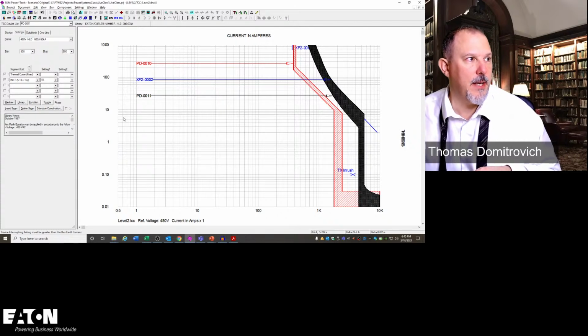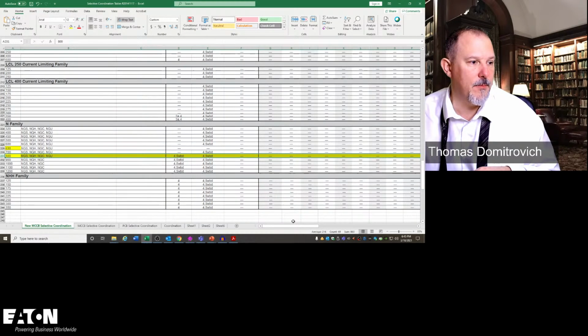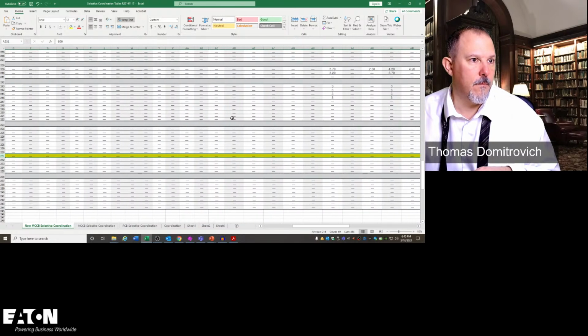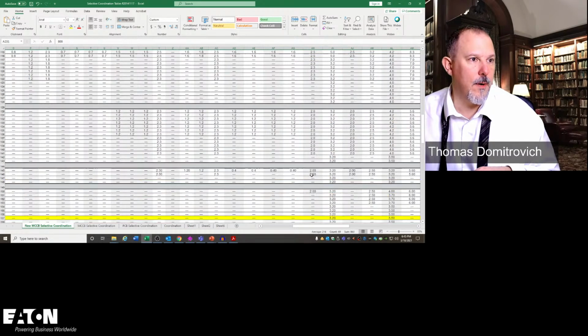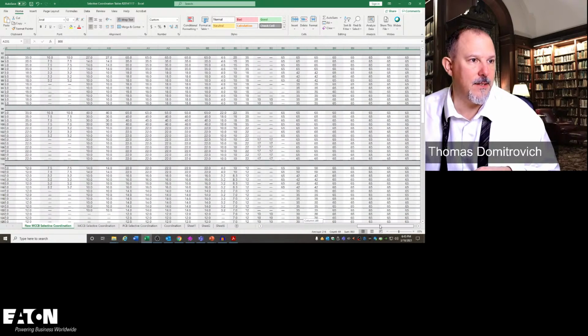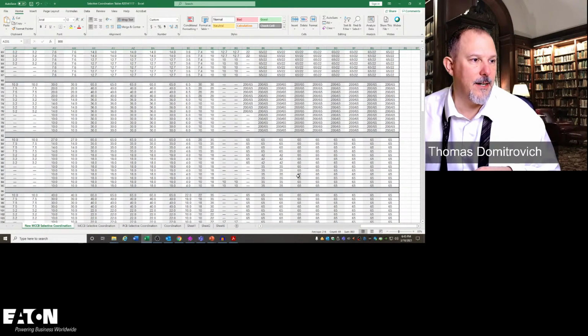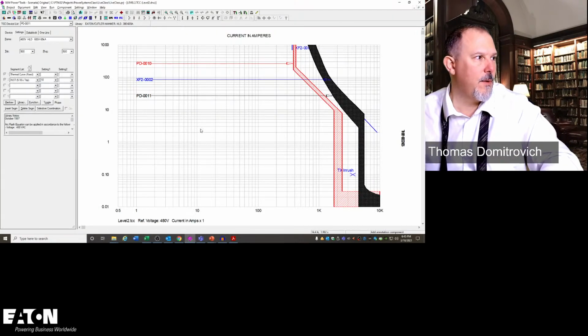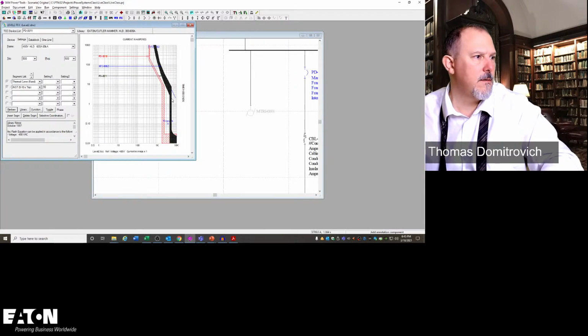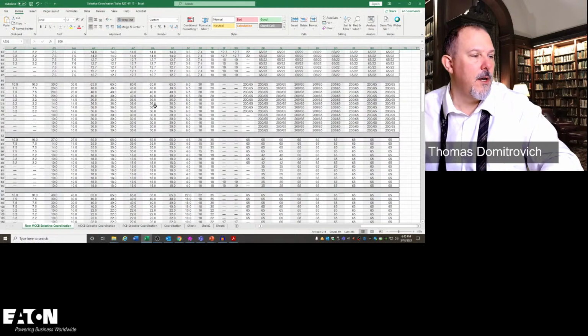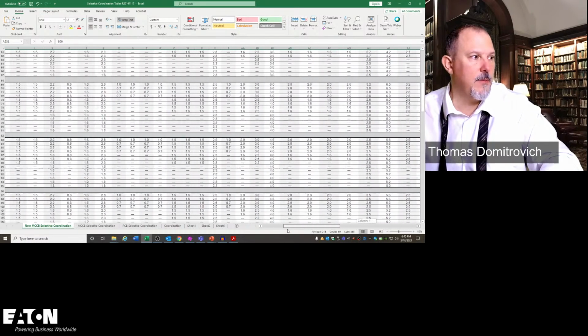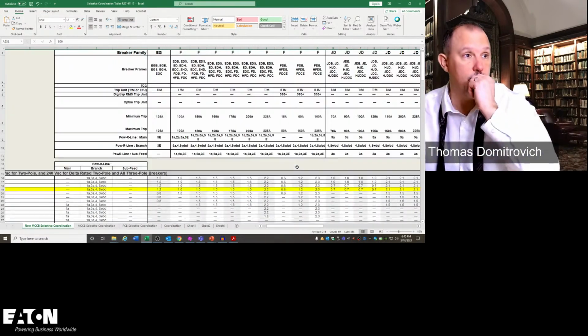That is going to be absolutely a tough one, because my table does not. I'd have to look at my newest tables to see, and that is an ND breaker. And I don't know why we did not go anything less. An ND 800 downstream of, what did I pick? I picked an LD on the primary. Okay, let's do this. An LD breaker. So let's do it this way.